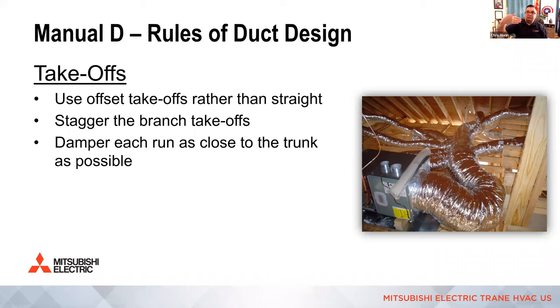If you can taper that takeoff, then it's easier for the air to make the turn into that branch and the equivalent length value is much lower. And you rely on balancing instead of cranking the velocity and the static pressure up, okay? Also, stagger the takeoffs off of the trunk. Don't have them directly across from each other because that provides a big pressure loss when you lose that much volume of air on what's on the other side.